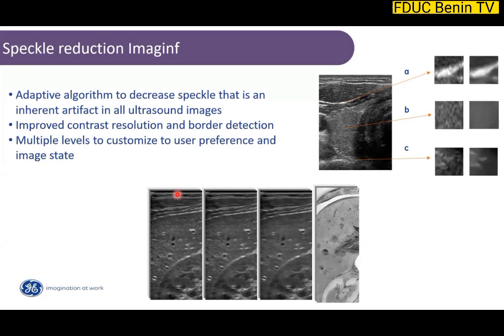And usually it's by step. It's 1, 2, 3, 4, 5, depending on the system. And if you see on this image, I'm reducing the speckle gradually, and here I have a very smooth image. Same here, you see that I can have different types of speckle on the image. And how do these algorithms in all our systems work? It's very simple. At the beginning, I talked about the ultrasound wave, and I told you that there are two main features of the ultrasound wave, the speed and the frequency. So we talked about the frequency, and now we're going to talk about the speed.